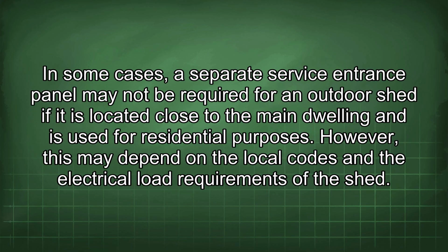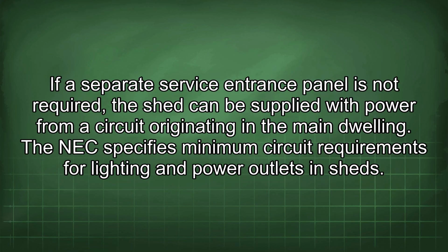In some cases, a separate service entrance panel may not be required for an outdoor shed if it is located close to the main dwelling and is used for residential purposes. However, this may depend on the local codes and the electrical load requirements of the shed. If a separate service entrance panel is not required, the shed can be supplied with power from a circuit originating in the main dwelling. The NEC specifies minimum circuit requirements for lighting and power outlets in sheds.